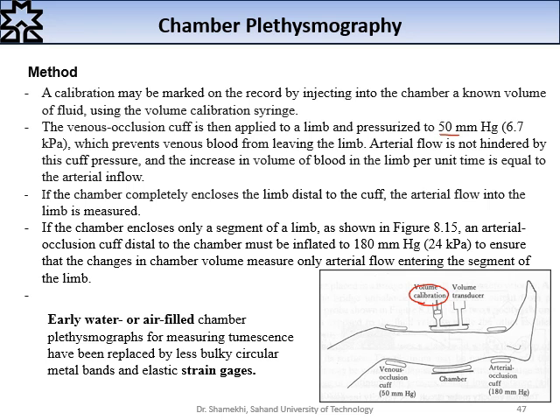to the arterial inflow. If the chamber completely encloses the limb distal to the cuff, the arterial flow into the limb is measured. If the chamber encloses only a segment of a limb, as shown in figure 8.15, an arterial occlusion cuff distal to the chamber must be inflated here, as I told you before, to 180 millimeter Hg to ensure that the changes in chamber volume measure only arterial flow entering the segment of the limb, a restricted, limited segment of the limb. Also, early water or air-filled chamber plethysmographs for measuring tumescence have been replaced by less bulky circular metal bands and elastic strain gauges.